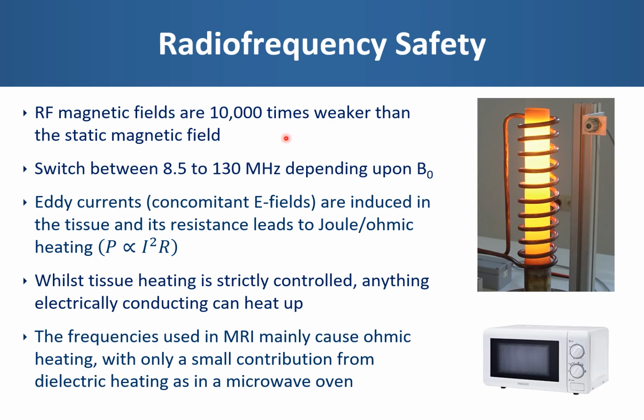Although the RF fields are 10,000 times weaker than the static magnetic field, they do switch between 8.5 and 130 megahertz depending on the strength of the static magnetic field. Because tissue is conducting, this alternating magnetic field will induce concomitant electric fields known as eddy currents within the tissue, and then the electrical resistance of the tissue results in joule or ohmic heating. So essentially we end up with an inductive heating process. And so while tissue heating is strictly controlled, anything electrically conducting about or in the patient can also heat up.